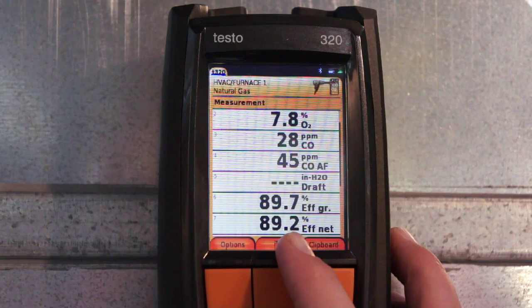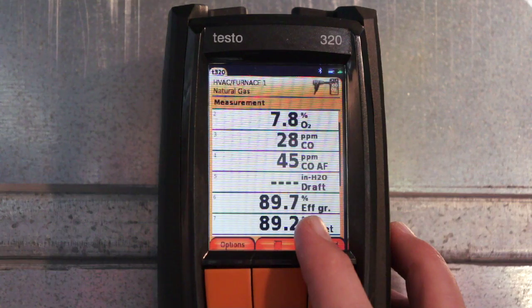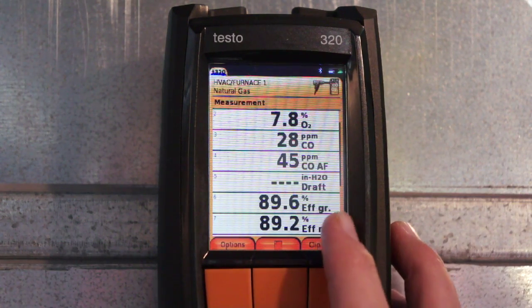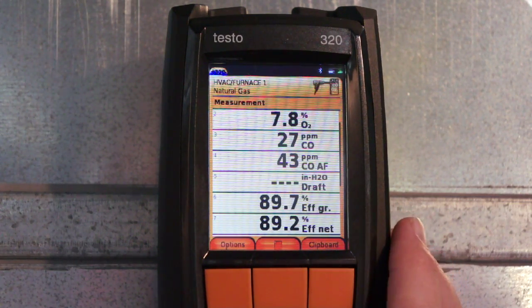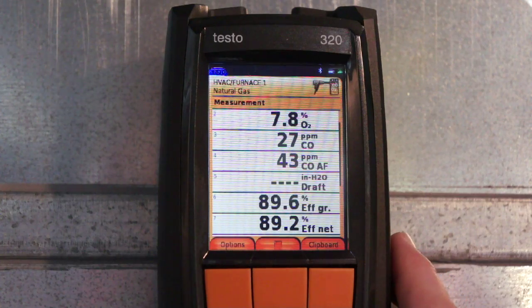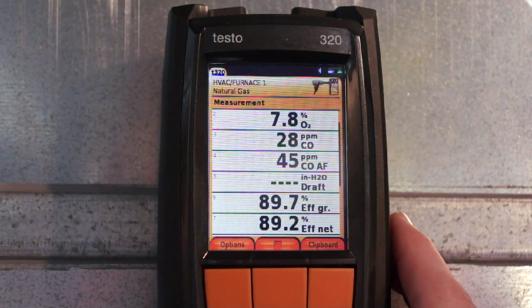On a 95% efficient furnace, obviously, the net would still be around this 89%, but our gross efficiency would be much higher. So if we were to measure the volume of condensate coming out of the trap on this, it would be fairly negligible. But it is condensing, and it is a condensing appliance.